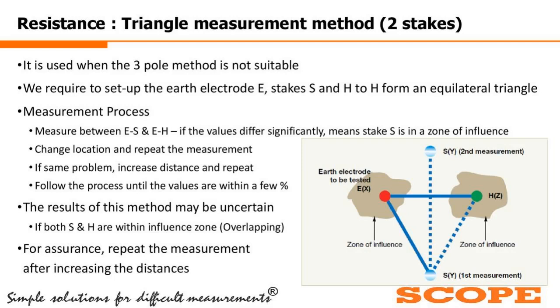Now, the resistance triangle measurement method, with two stakes. It is used when the three-pole method is not suitable. We need to set up the earth electrode E, as shown by the red dot, and two stakes, S and H, as shown by the blue and green dots, so that S, H and E cumulatively create an equilateral triangle.